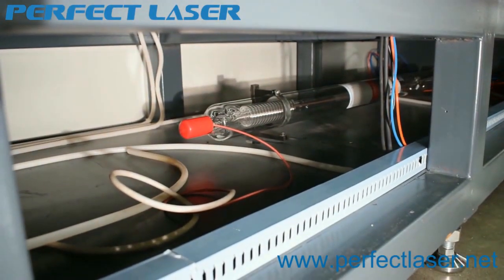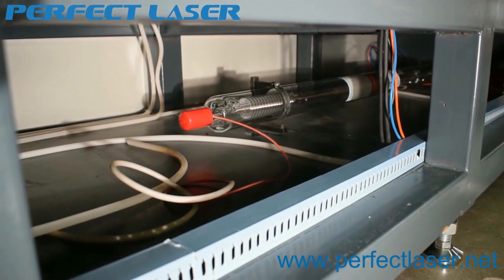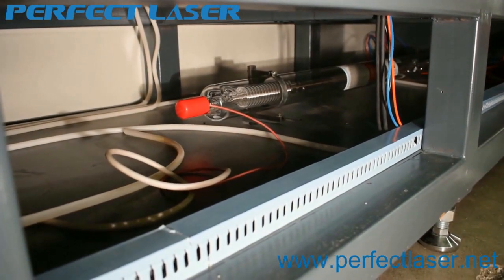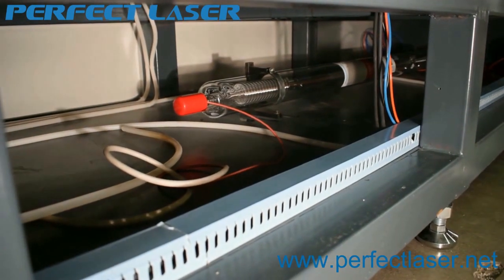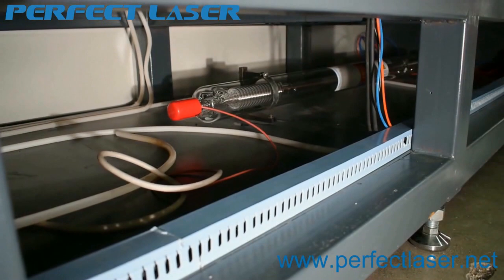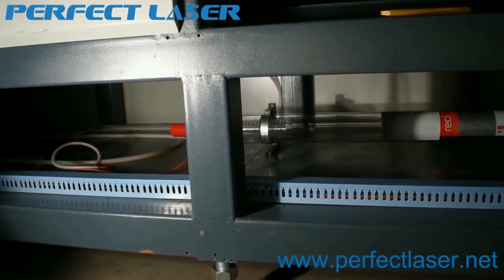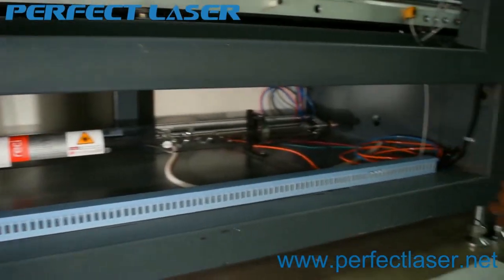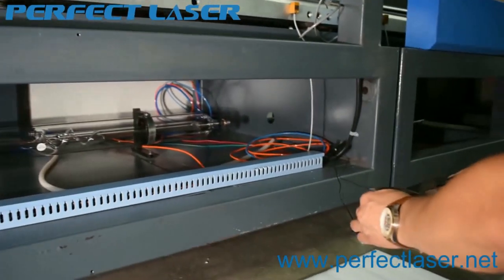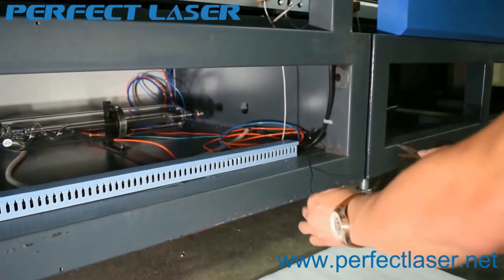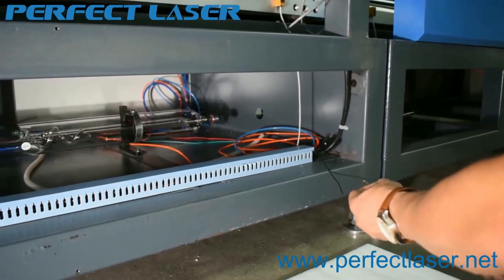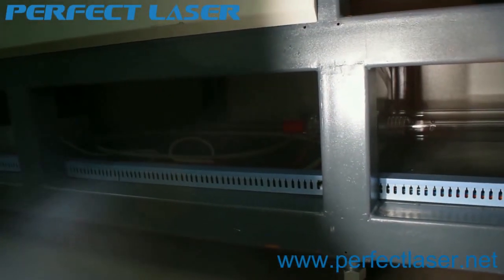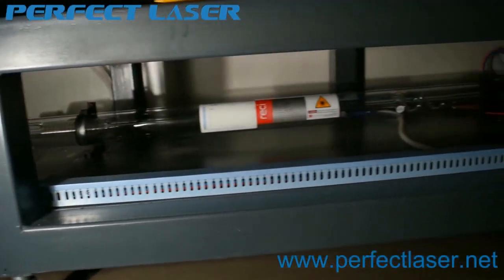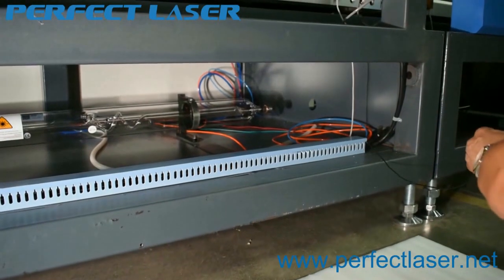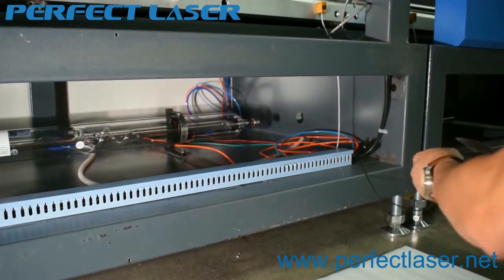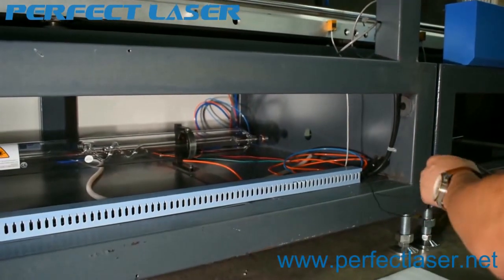Because this red cable is the high voltage cable, we should make sure you use it safely. So we need to use the red cover to protect it. The human body cannot touch it. Okay, just now we connected this side. Now we will change into another side. This is the right side, and you will see there is a black cable. This cable is a low voltage cable. That means on the left side there is a high voltage cable, and on the right side there is a low voltage cable. We need to connect the low voltage cable into the other side of the laser tube.